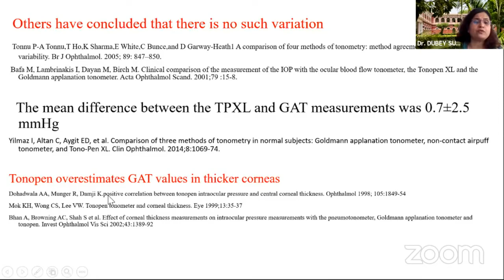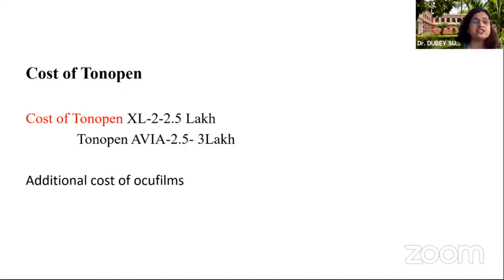And some studies suggest that there is not much difference. Again, TonoPen overestimates GAT values in thicker corneas. So it is affected by corneal thickness. And so the cost is 2 to 2.5 lakhs, but additional cost of OcuFilms. So when you compare all these tonometers, GAT is the gold standard, we know. However, the maintenance cost would be high for the TonoPen and iCare tonometer because of these disposable probes and OcuFilm.